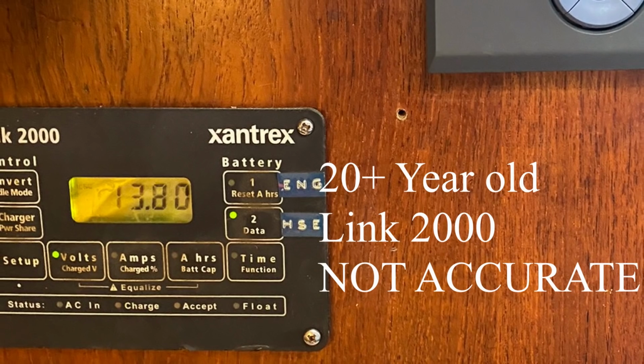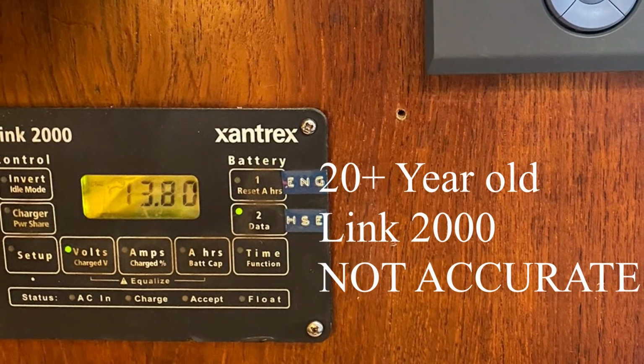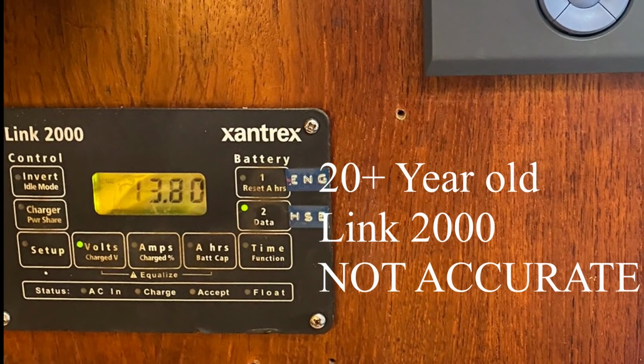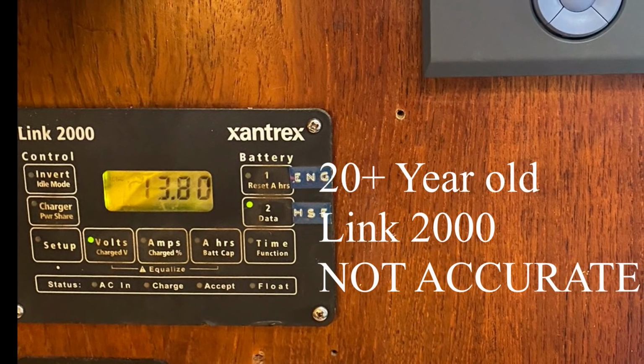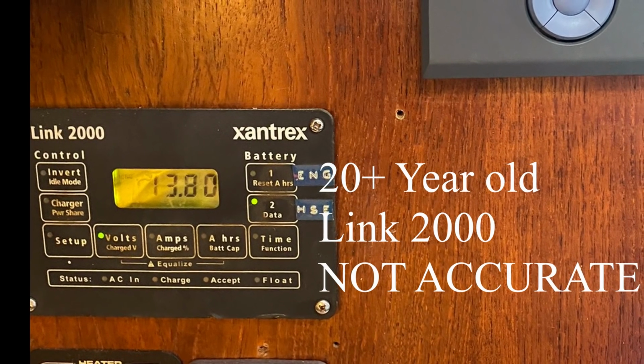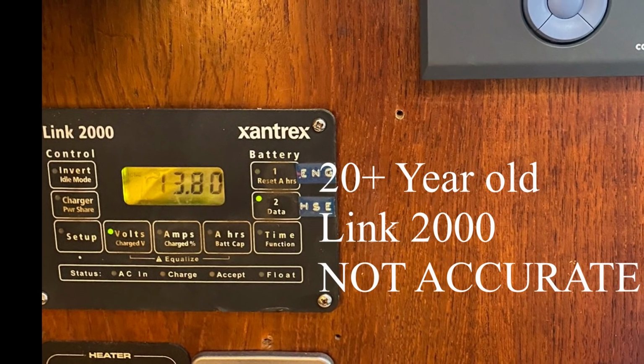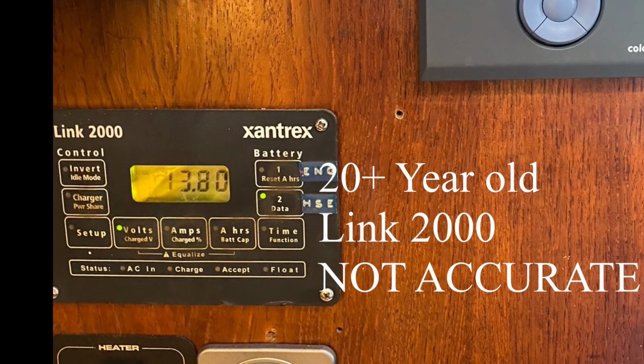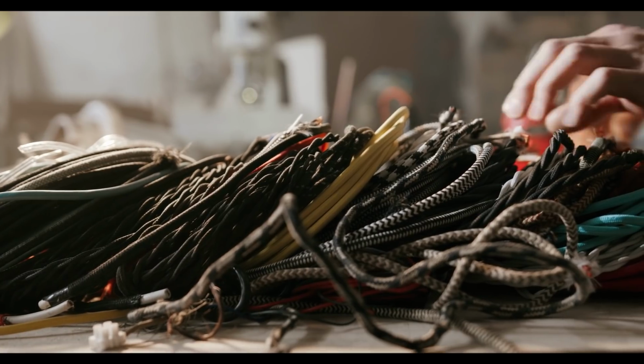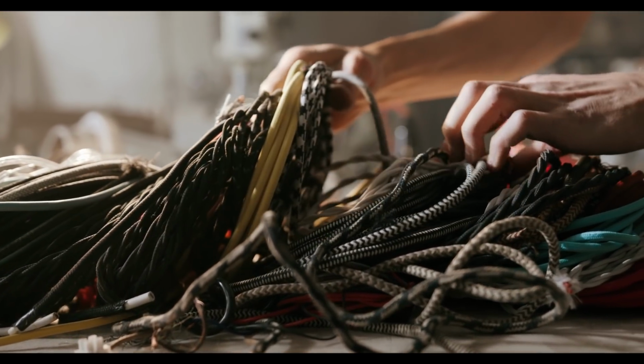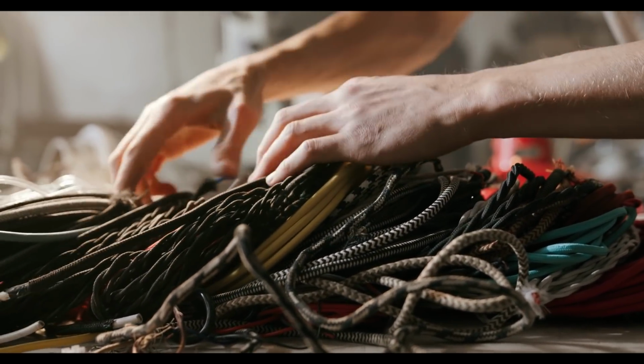Just because you have a battery monitor doesn't mean after all these years it's still working effectively. I have an old Link 2000 battery monitor, but we've always known we have bad wiring practice on Brick House. We've used undersized wire gauges and improper fuses and circuit breakers, but the Link 2000 uses a shunt like many battery monitors do, and ours, due to inadequate labeling, bad memory, necessity, etc., has often been used as a negative bus bar rather than the dedicated shunt.